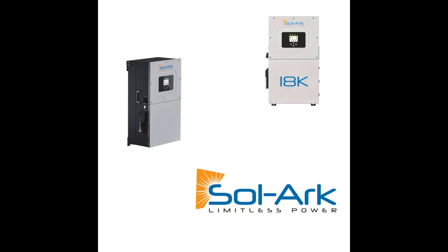For the 18K, you can use up to 28.8 kilowatts of solar connected to the MPPTs. And you can also have connected underneath that value too. That's perfectly fine. As long as it meets the customer's end needs and goals, it'll be in a good range, and also for charging the battery. Then max AC coupled inputs, 19.2 kilowatts. That's the feature I talked about on the gen port of the inverter. If you do want to add or retrofit that existing AC coupled array, that's your maximum there.